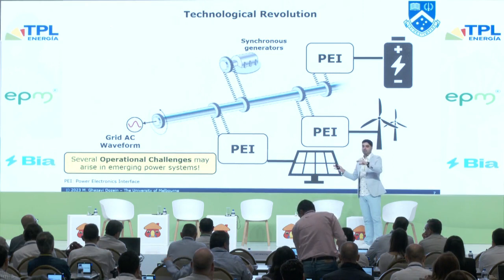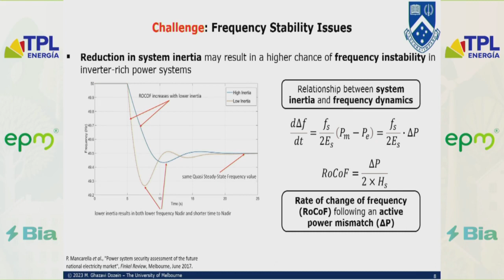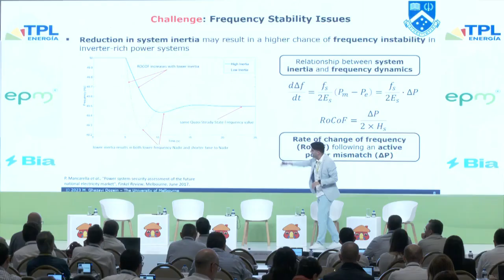The first challenge is well known: frequency stability. As you increase the number of inverters and take out synchronous machines, the system loses the luxury of inertia from synchronous machines, leading to frequency instability. As you lose this kinetic energy, for a given contingency, there's a clear contrast between low inertia and high inertia systems.